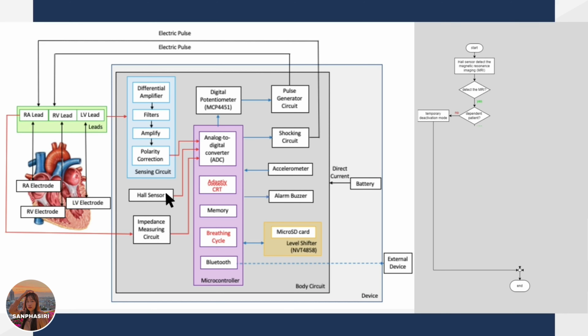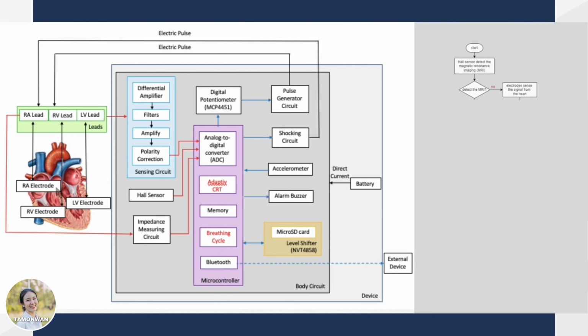Another is temporarily deactivated mode, which is for the independent pacemaker patient. This mode is neither sense nor shock, to prevent inappropriate pacing or shock. For the mode that the Hall sensor doesn't detect the MRI, the electrodes in each chamber will sense the signal and send all of them through the leads. The signal goes through the sensing circuit to be filtered and amplified. All of the obtained data are stored in the memory of MCU.